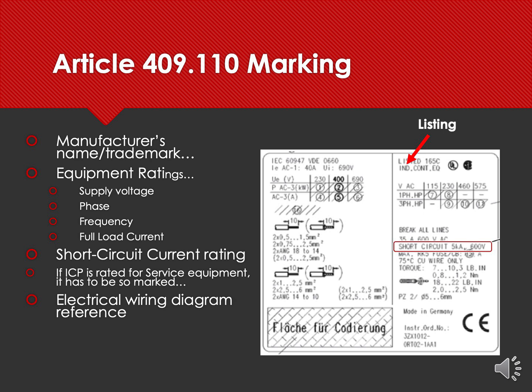The short circuit current rating also needs to be on here, which we discussed in the definitions section. If it's going to be used, as we said, for service equipment, it needs to be so marked and for that kind of duty. And then finally, the electrical wiring diagram reference. It is an OSHA requirement that all fixed facilities have accurate schematic diagrams of the facility. And so this should show up on a schematic diagram that not only has a diagram of how it fits into the overall system in the plant, but also the internal wiring of this piece of equipment as well. So let's go to the next slide.